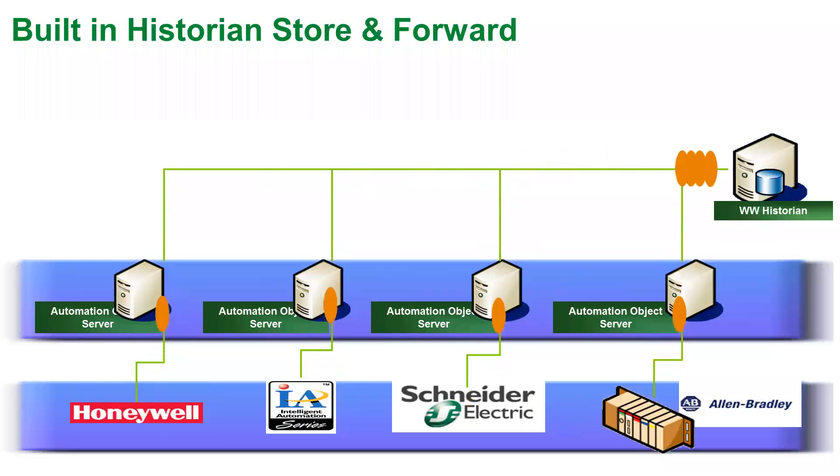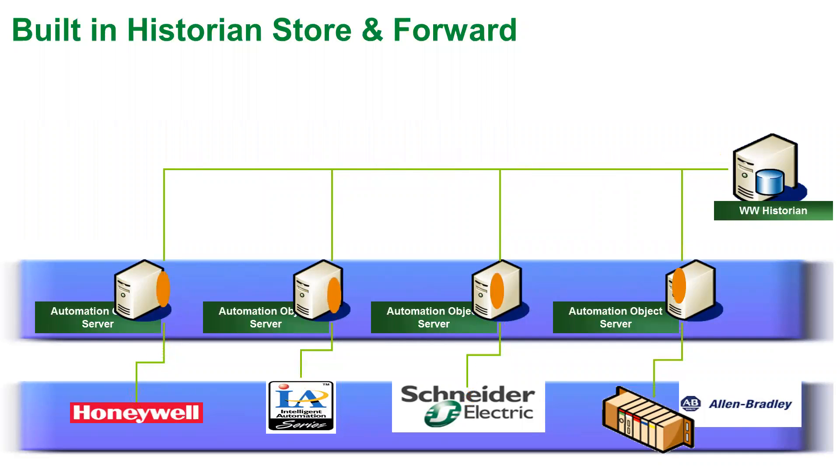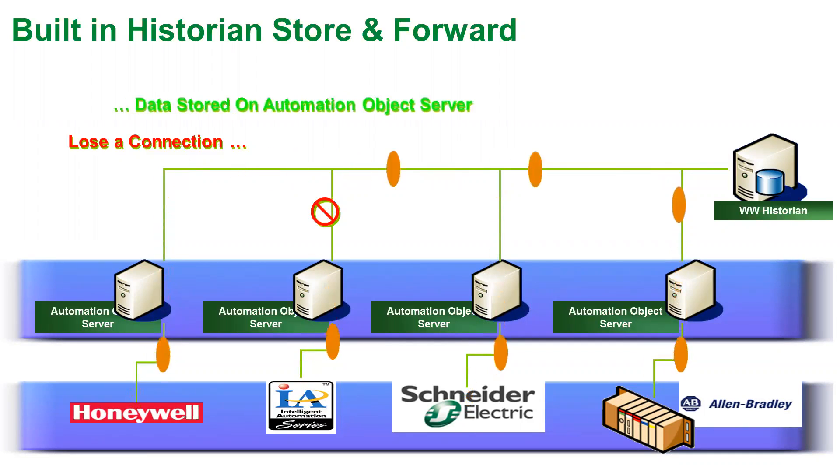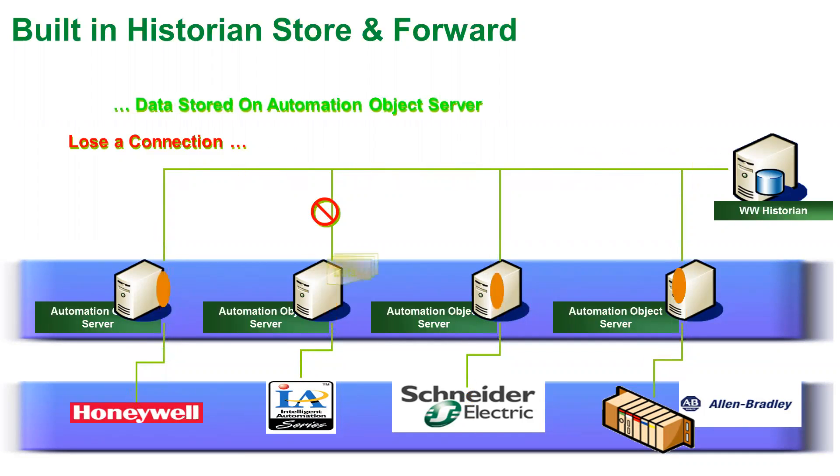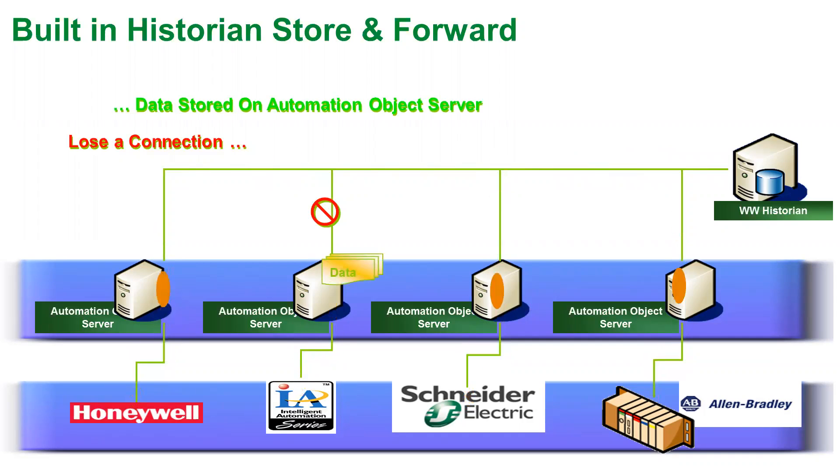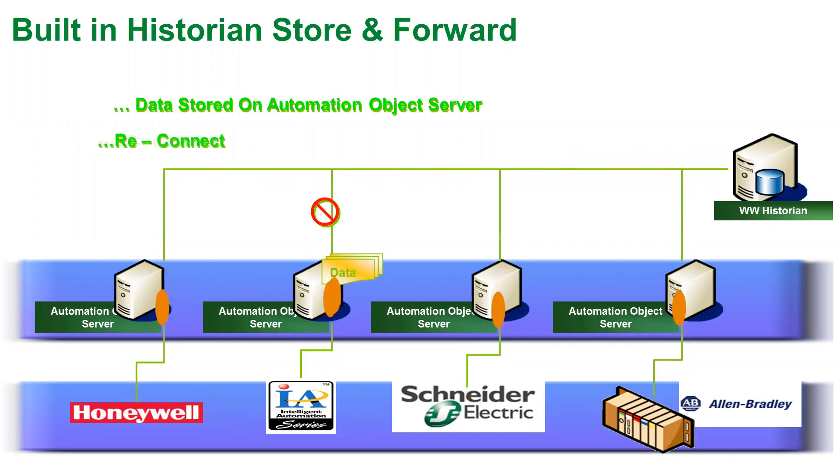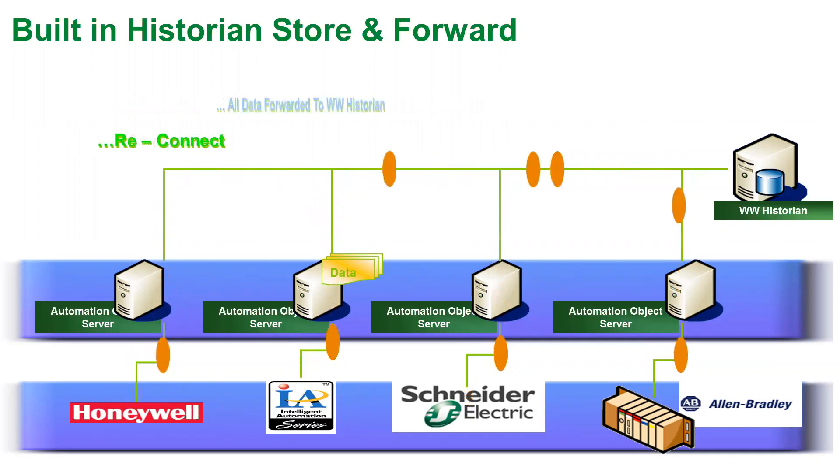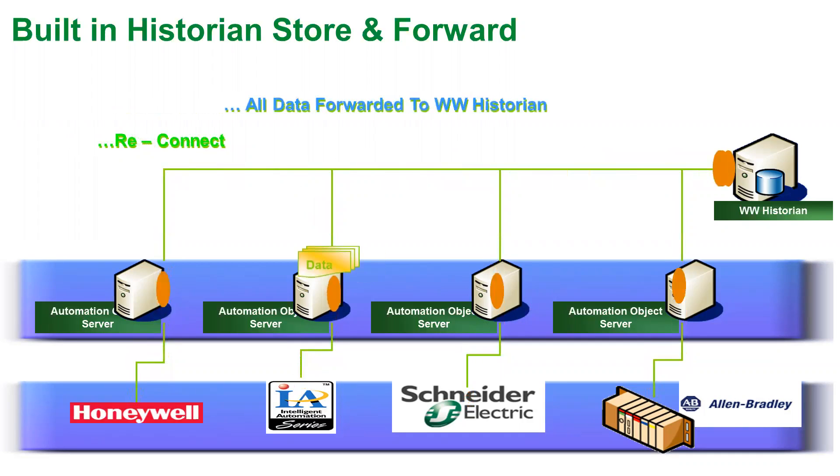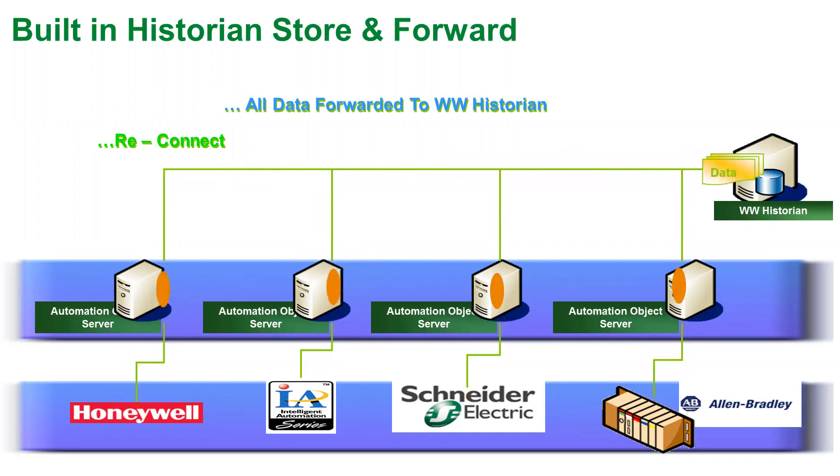Engines also provide store and forward data to the Wonderware historian. If a connection is lost to the historian, the engines will continue to store and buffer the data. Once the connection is restored, the engines automatically backfill the historian so there's no loss of data.